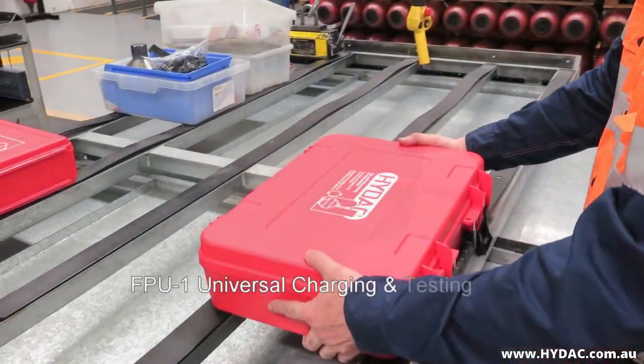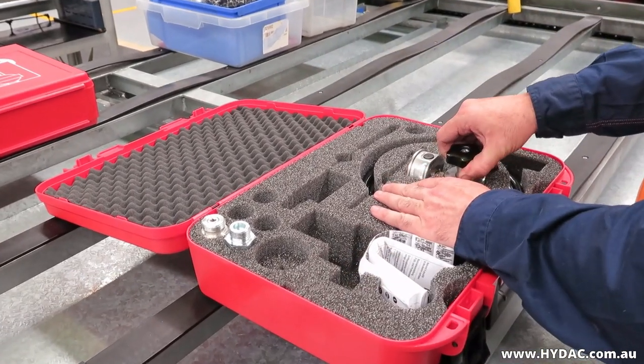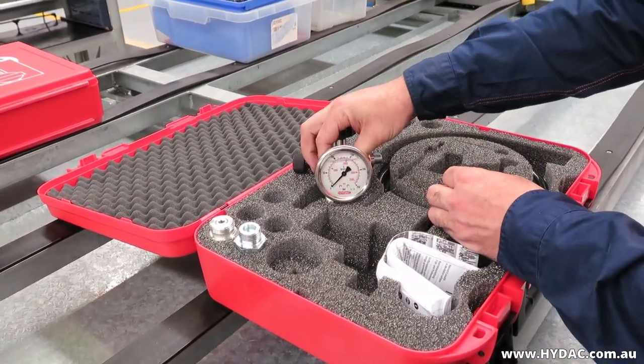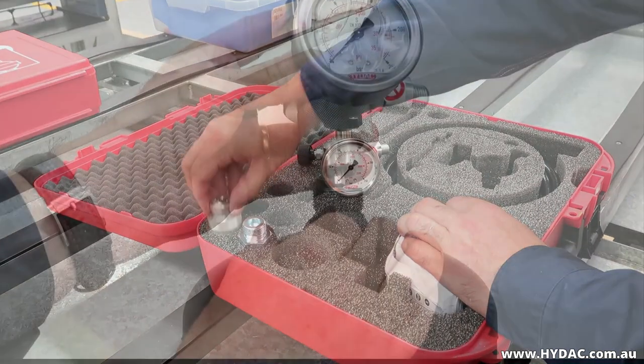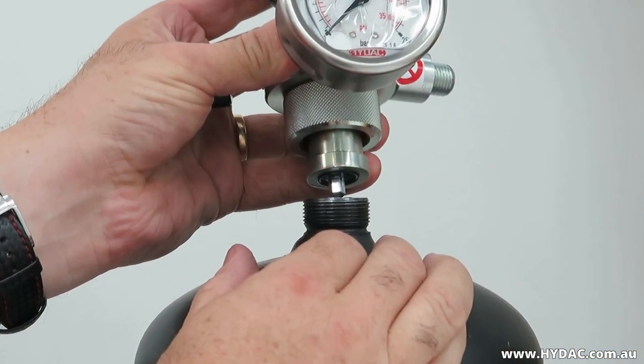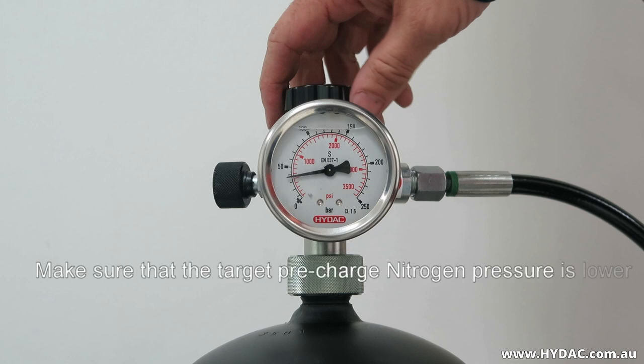The HYDAC FPU1 universal charging and testing unit can be fitted directly to HYDAC diaphragm and piston accumulators. The accumulator gas valve will be opened and resealed by operating a hex key in a socket head cap screw, and during the charging process it will be operated by the main spindle of the charge head.